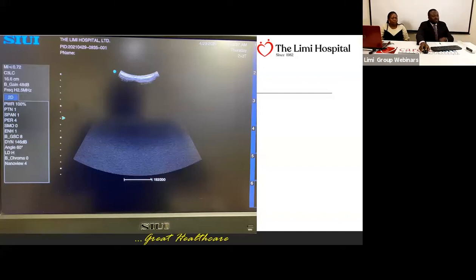You could have a transvaginal endocavitary probe that can do even higher frequencies, but they have limited depth of view. If you use a transvaginal scan, you can see maybe to a depth of about 8 cm, not farther. But it's used in specific cases in first trimester scan.